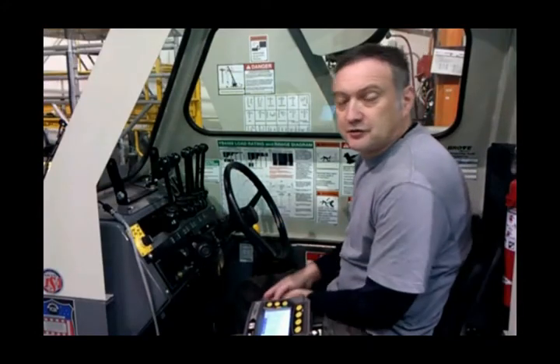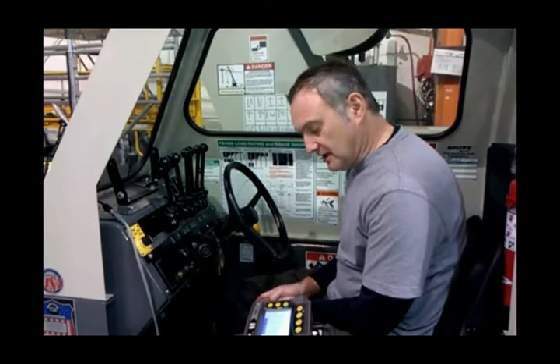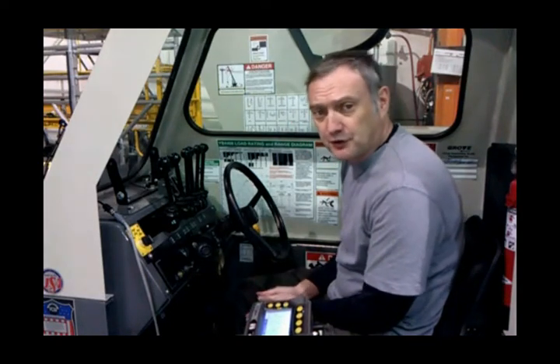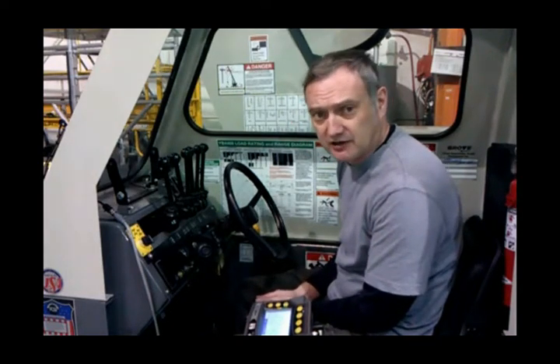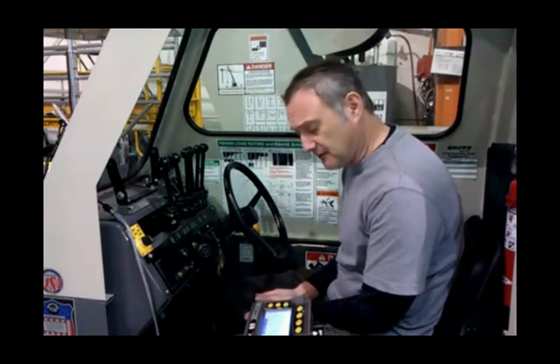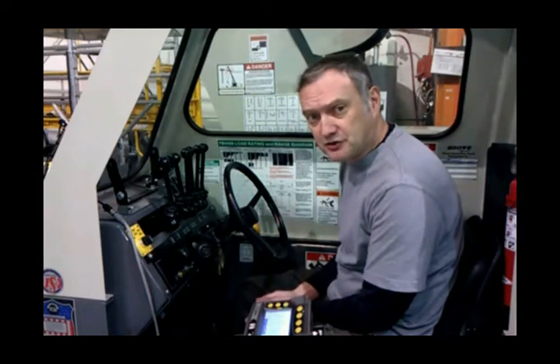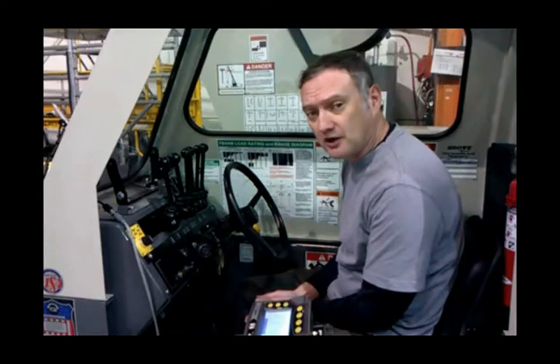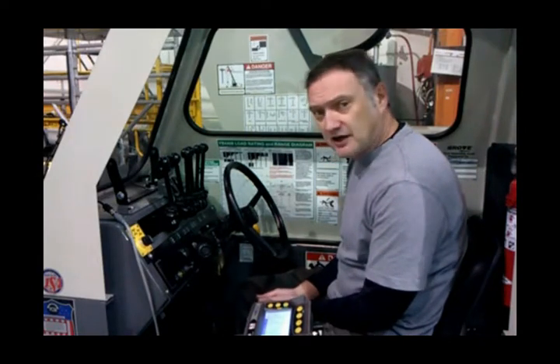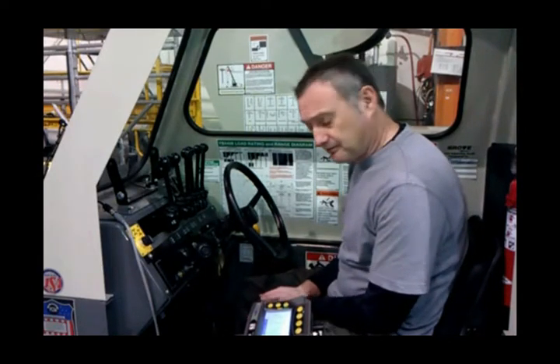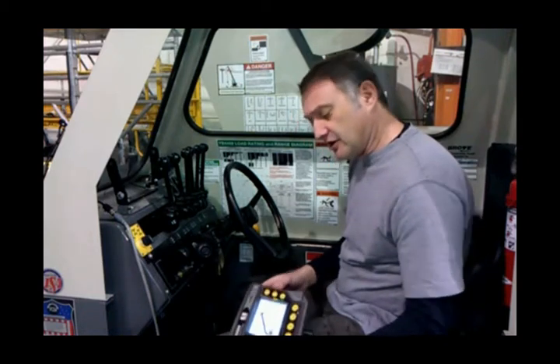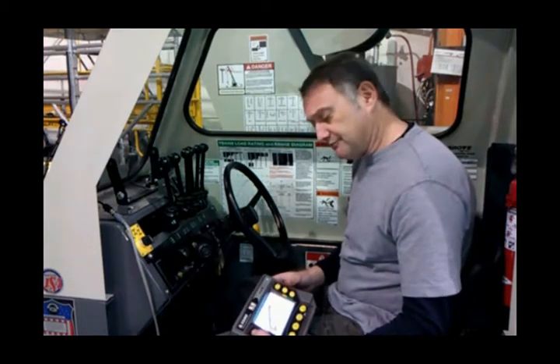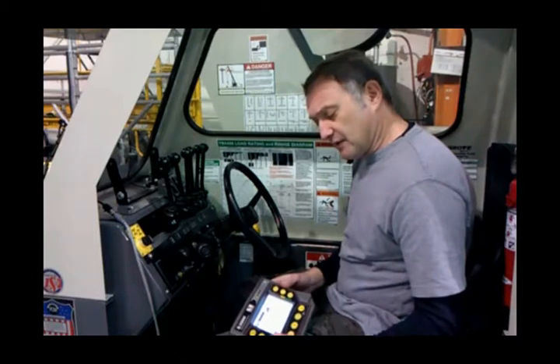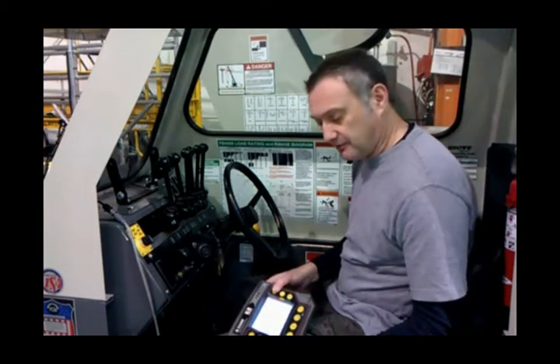All right, we're going to discuss transducer calibration. In order to determine whether or not your transducers are good, of course, first you have to know what they're supposed to be indicating in a known state. If you go to section 7 in the troubleshooting guide, I'm going to discuss what I'm about to do. So right now I'm in diagnostics. In case you forgot how to get there, hit button number 1. You get your menu, scroll down, select diagnostics, and hit the check mark.